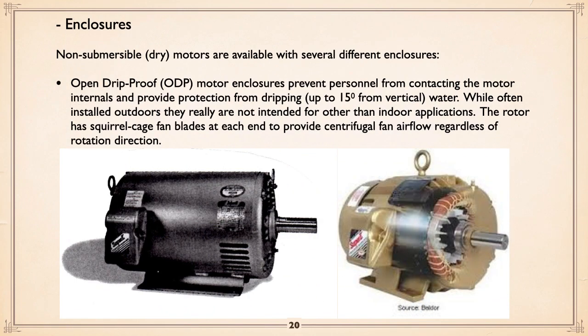Now we know basically how a motor works. Let's get into a little more of the details of motors in general. Motors come in different enclosures. In terms of dry motors, in other words non-submersible, there are several different ways of doing it. The most common is what they call open drip proof. In other words, the enclosure is designed to keep people's fingers out of it, getting shocked or whatever, and provide protection from dripping up to 15 degrees from vertical. While often installed outdoors, they're really not intended to be installed outdoors.